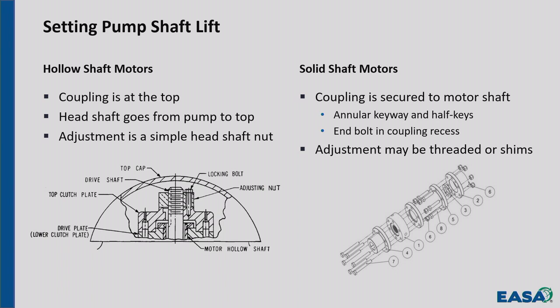You got to lift that pump shaft up. Two ways it's done. Hollow shaft, there's a nut up on the top. Really simple. You just tighten the nut up and lift it up. If it's a solid shaft, the coupling has some provisions in it. Some of them have threaded fittings where you thread the couplings together or apart to raise or lower the shaft. Some of them have spacers that need to be put in.